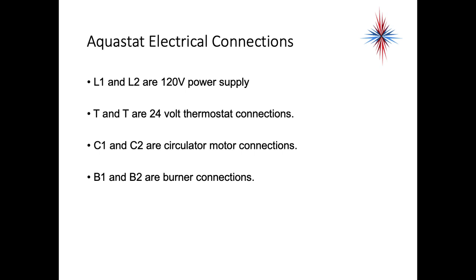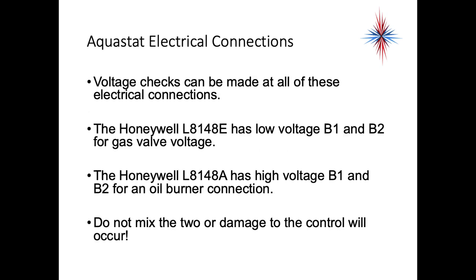Aquastat electrical connections are pretty much standardized with very few differences. L1 and L2 are the 120-volt power supply. T and T are the 24-volt transformer or thermostat connections. C1 and C2 are circulator motor connections, and B1 and B2 are burner connections. Voltage checks can be made at all of these electrical connections. The Honeywell 8148 has low voltage B1 and B2 for gas valve voltage, while the Honeywell 8148A has high voltage B1 and B2 for oil burner connections. You must make sure you have the correct aquastat — do not mix up the two, or damage to the control, gas valve, or burner will occur.